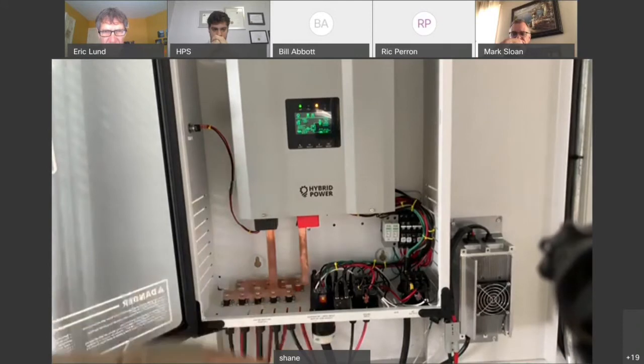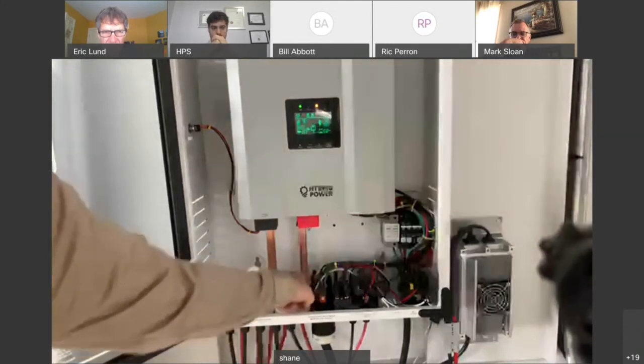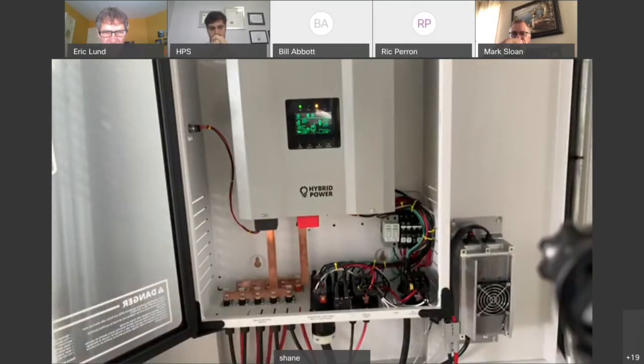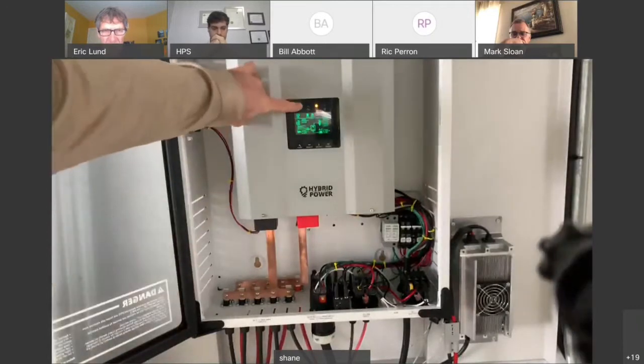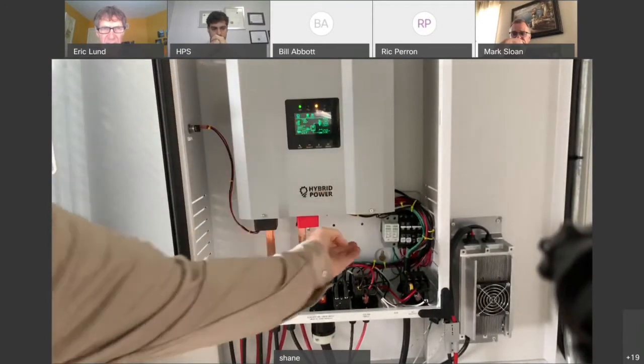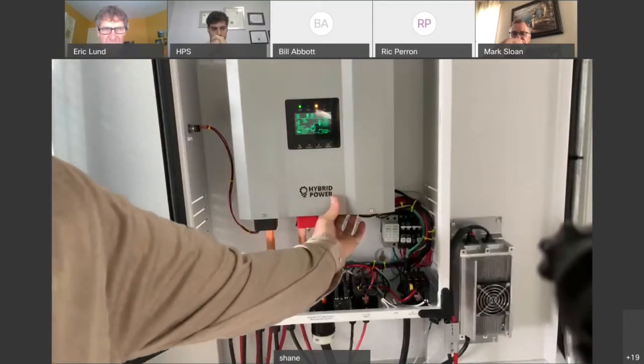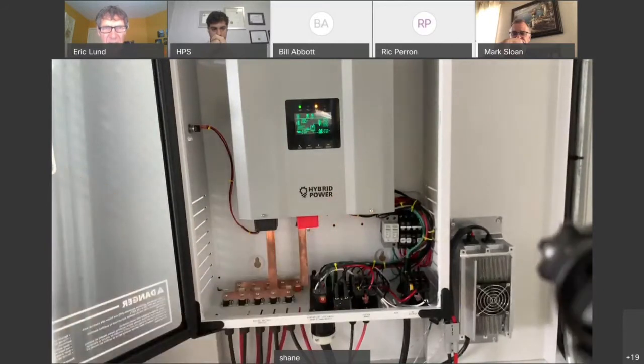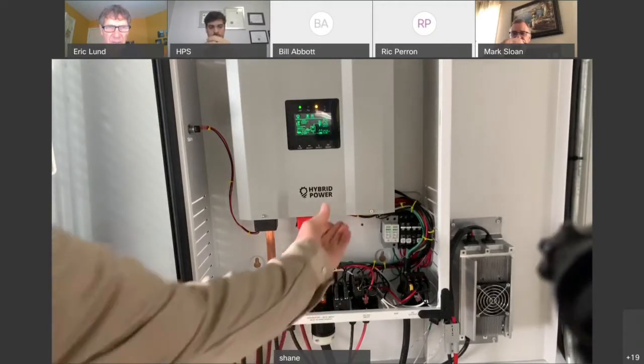All right, so that relay's pulled in. I do not have any voltage on this guy because they're interlocked. So as you can see here, we still don't have our input coming in. That's because our breaker underneath is off. So I'm going to turn it on. And keep in mind, we don't have the delay on the charging circuit right now on this firmware. So it will start to push current into the batteries immediately.